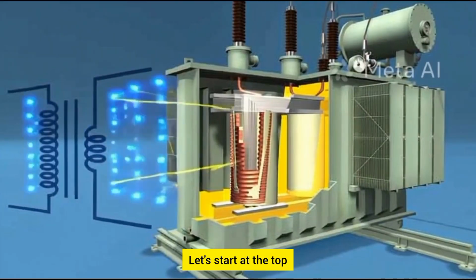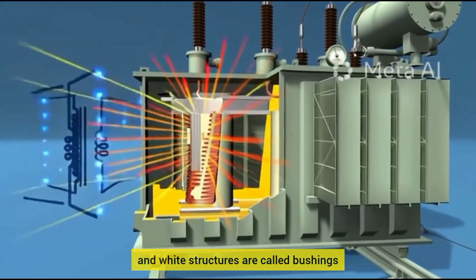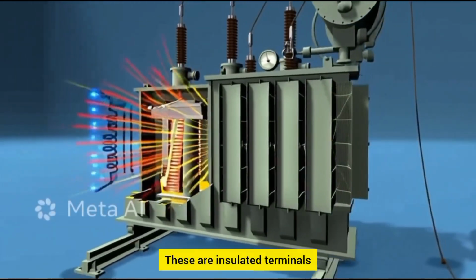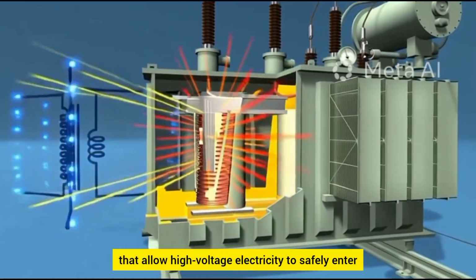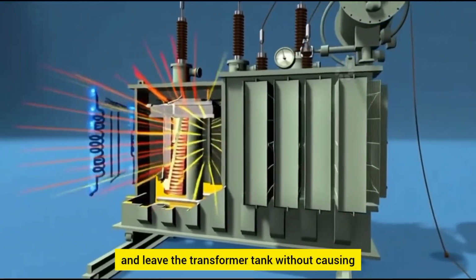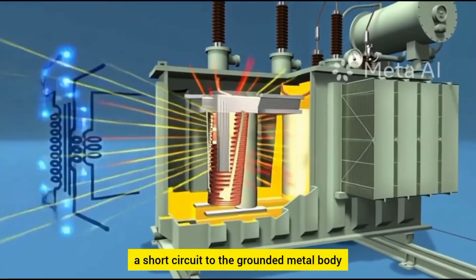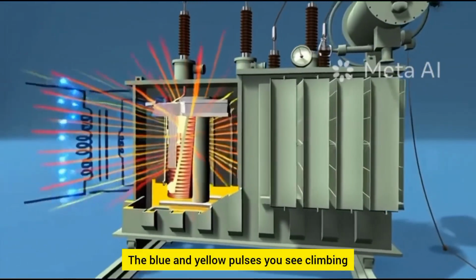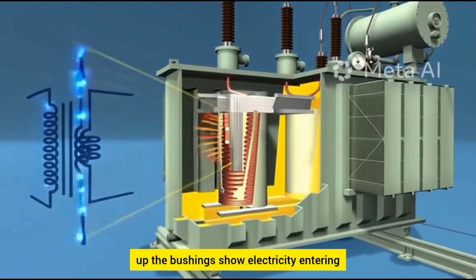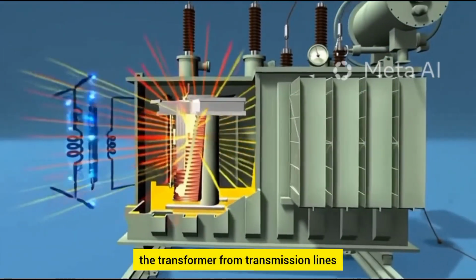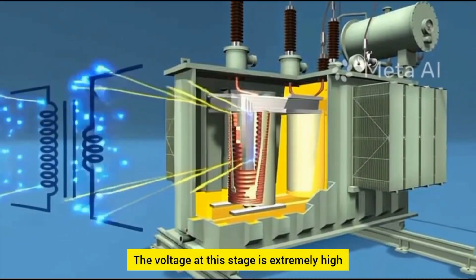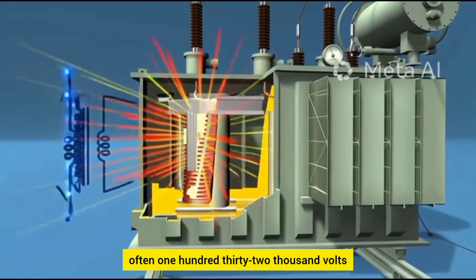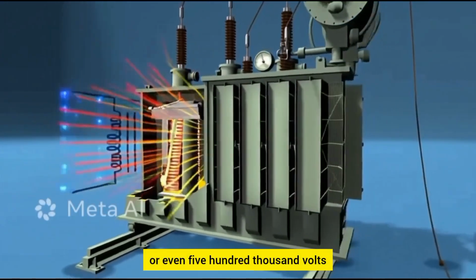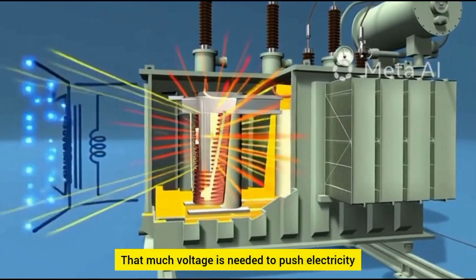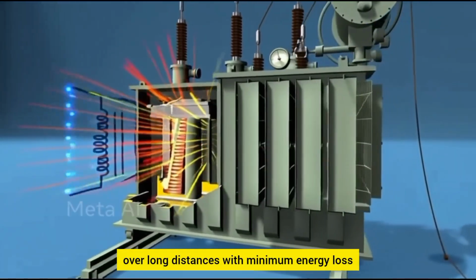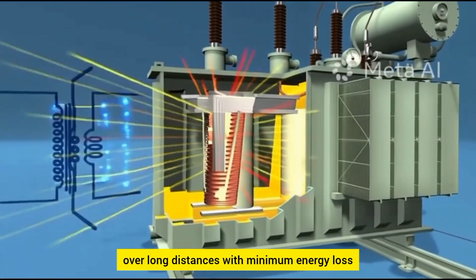Let's start at the top. The tall, black and white structures are called bushings. These are insulated terminals that allow high-voltage electricity to safely enter and leave the transformer tank without causing a short circuit to the grounded metal body. The blue and yellow pulses you see climbing up the bushings show electricity entering the transformer from transmission lines. The voltage at this stage is extremely high, often 132,000 volts or even 500,000 volts.